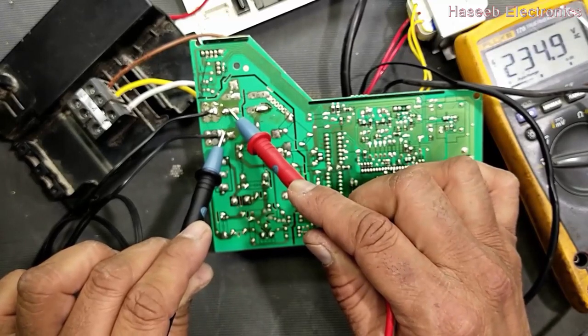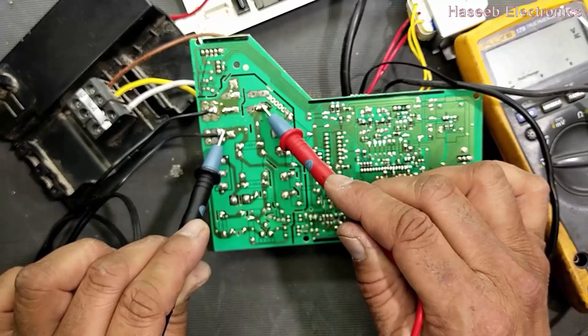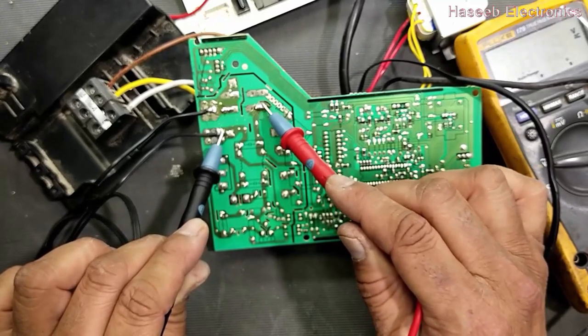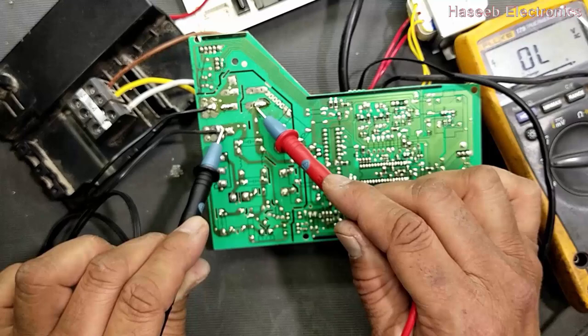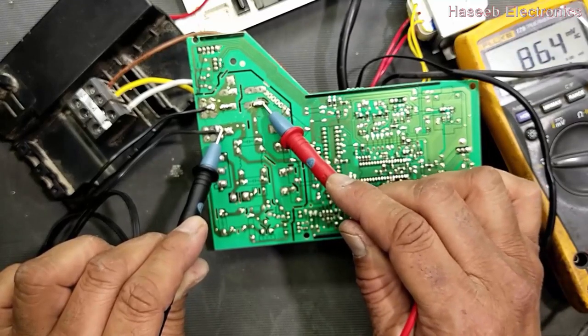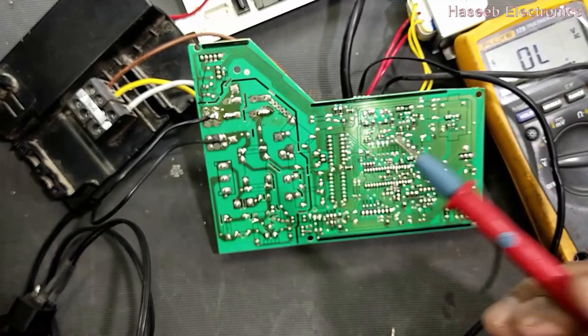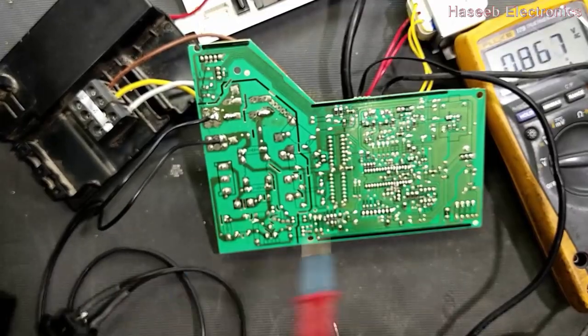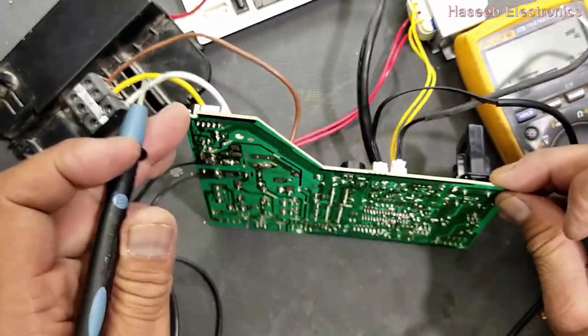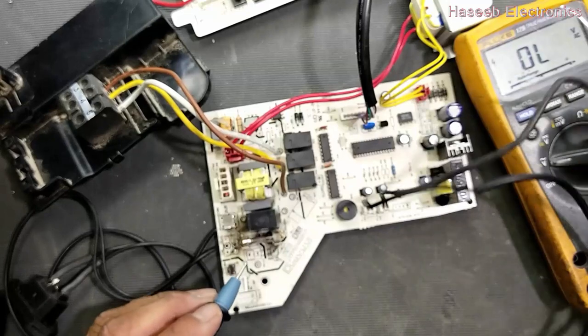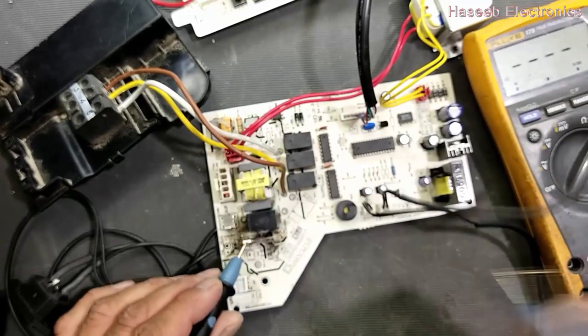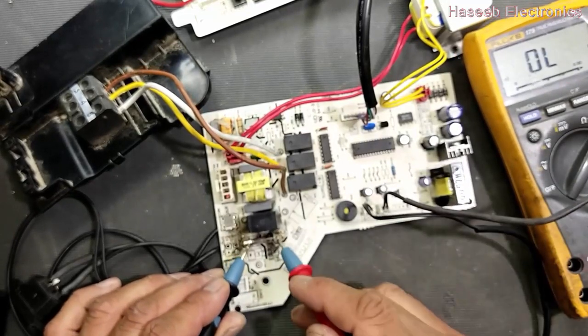Input of the fuse is 230. There is no output voltage at the fuse's second end. So that means the fuse is open. We have no voltage. So, as we know, for practice, set the multimeter to ohm continuity.